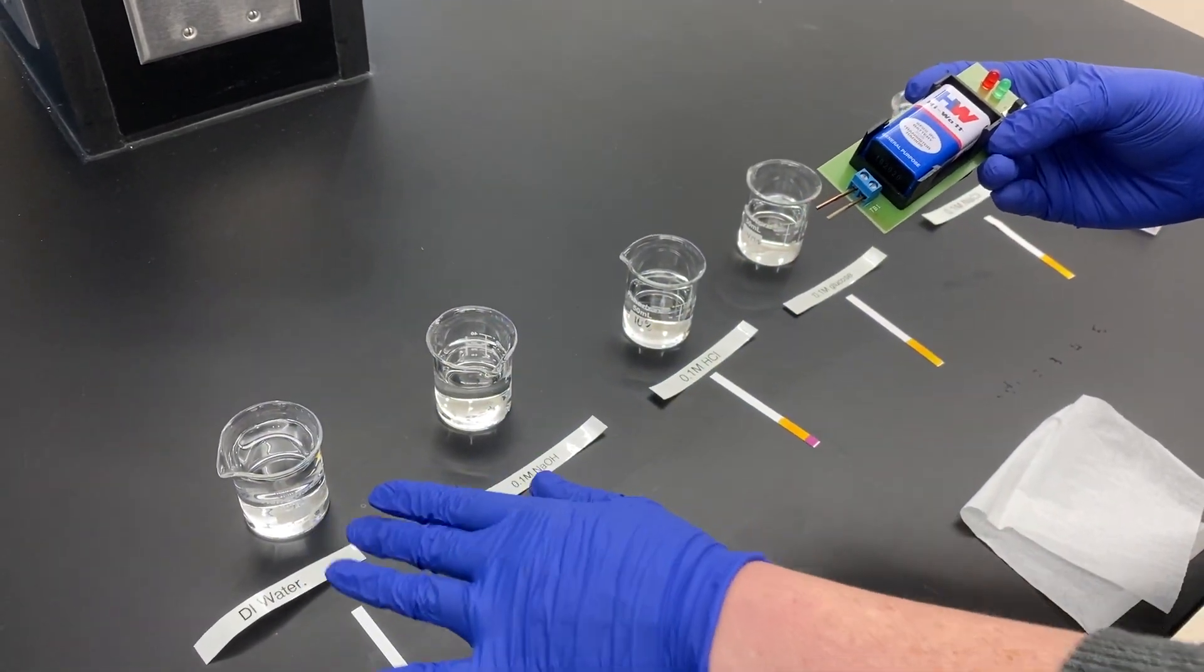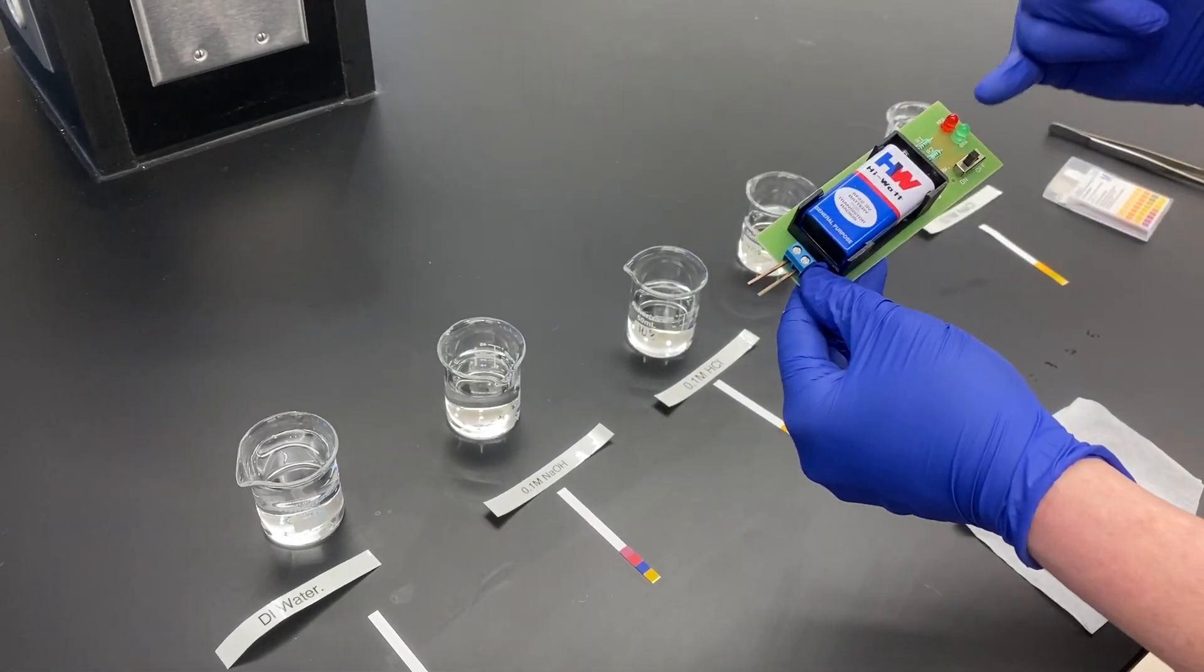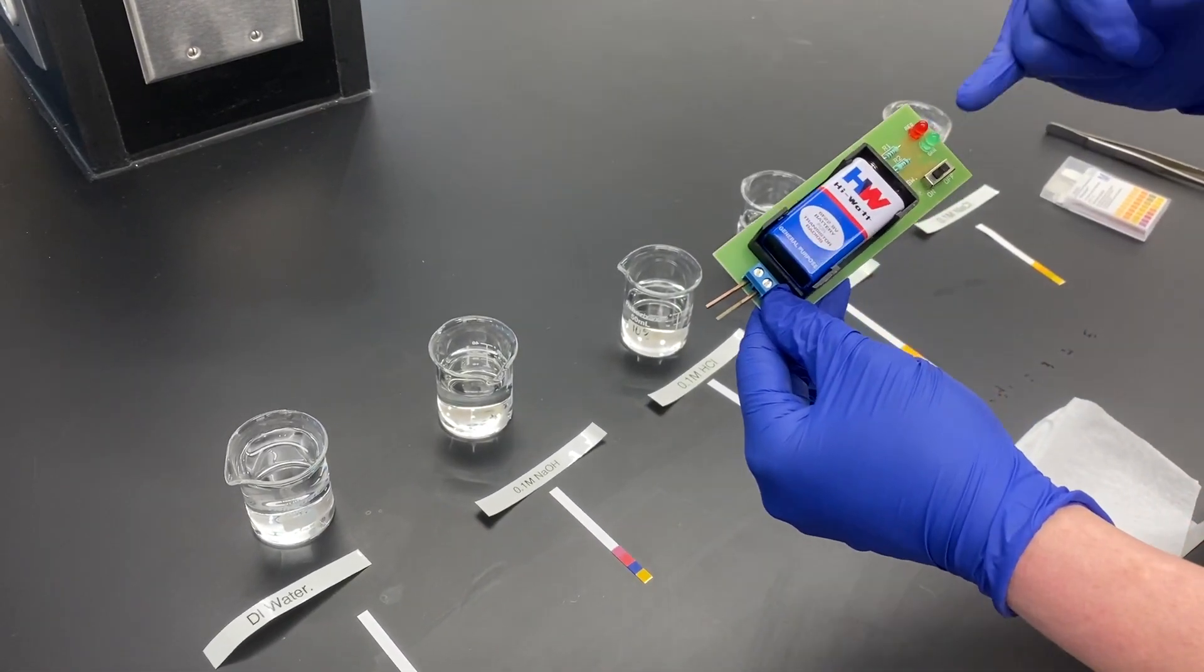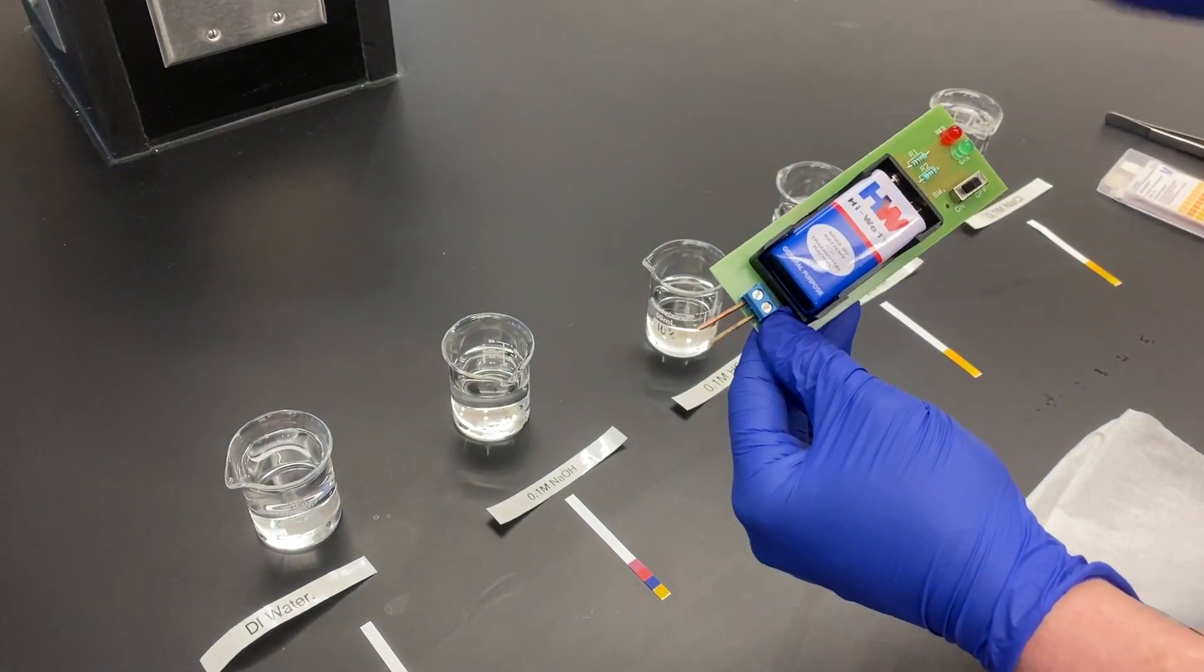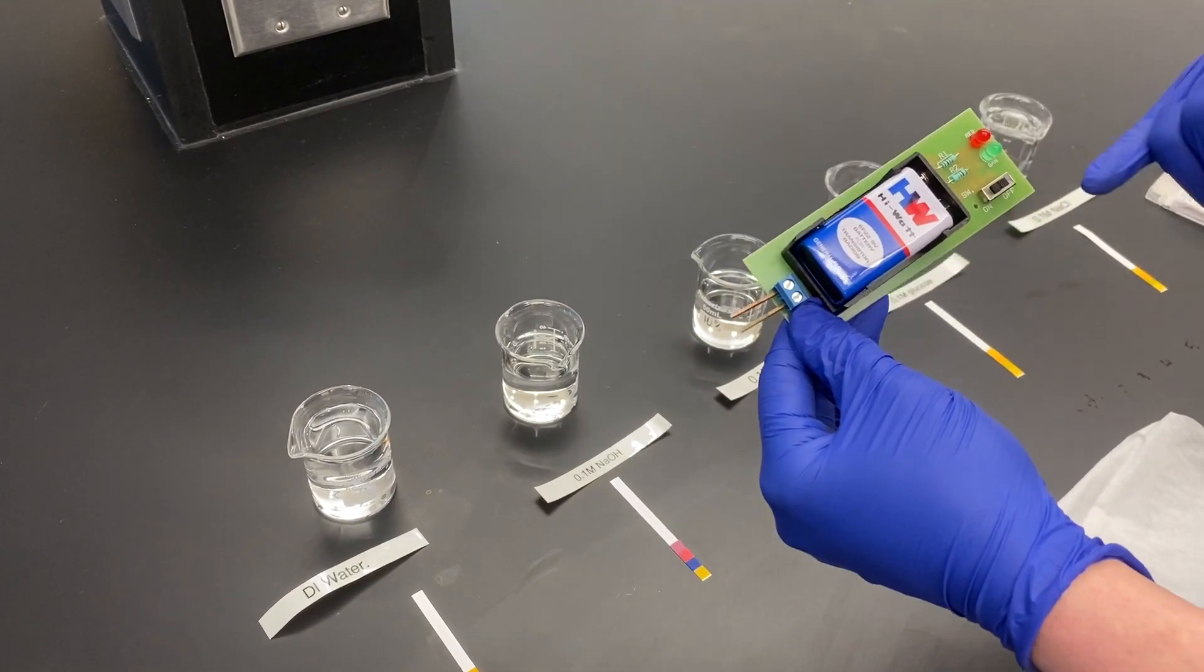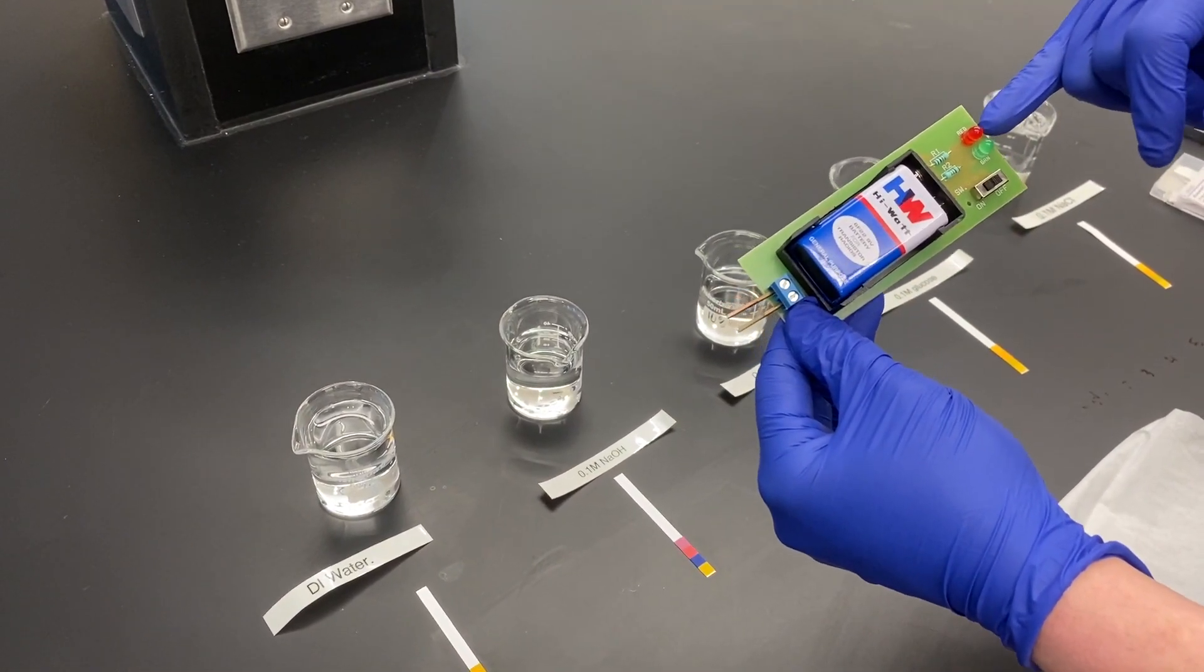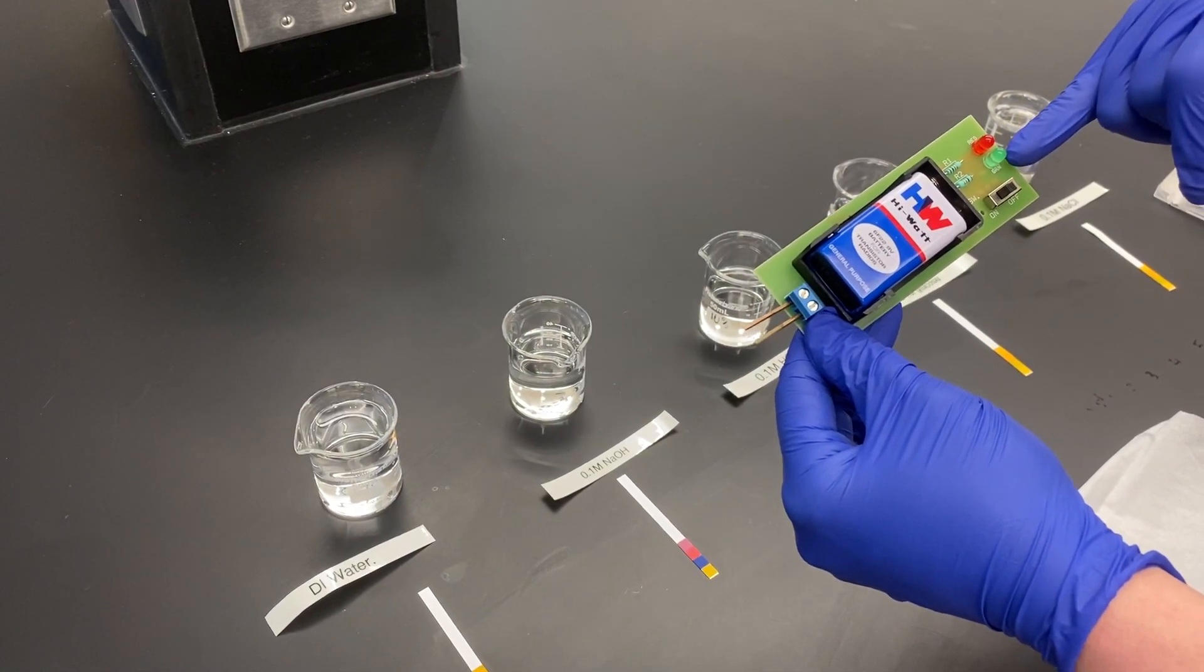We detect this as coloration of these two lights. As the lights light up, the more conductivity you have, the more ions you have, which will dictate whether you see just red, faint red-green, or distinctly green if it's very high conductivity.